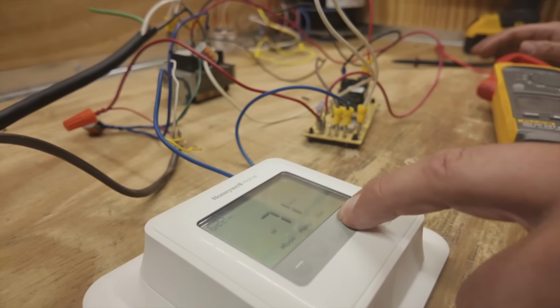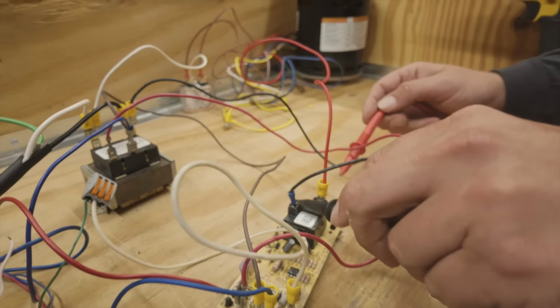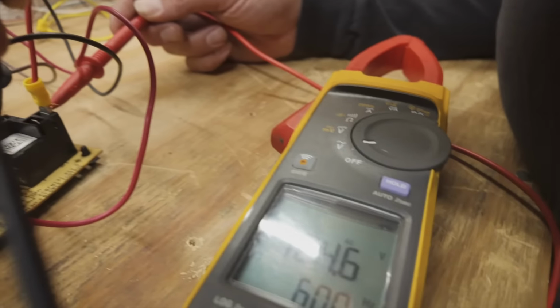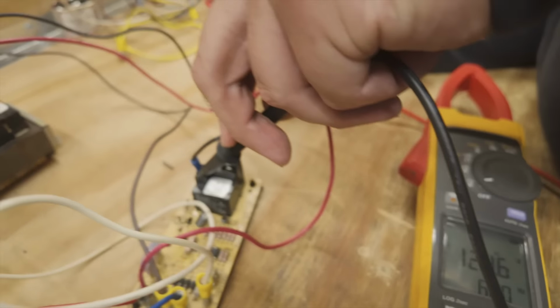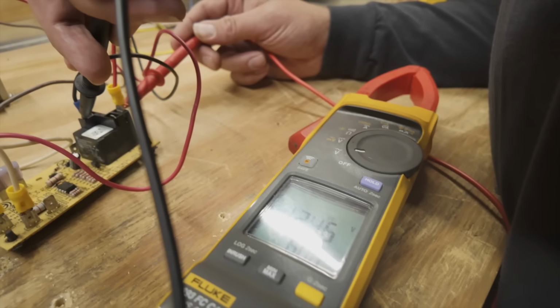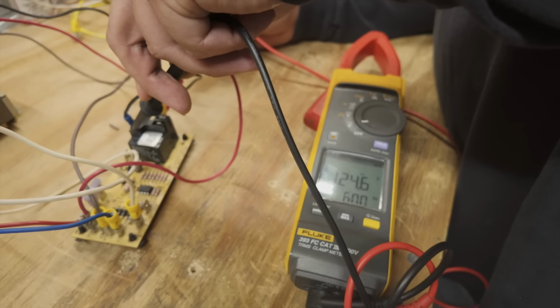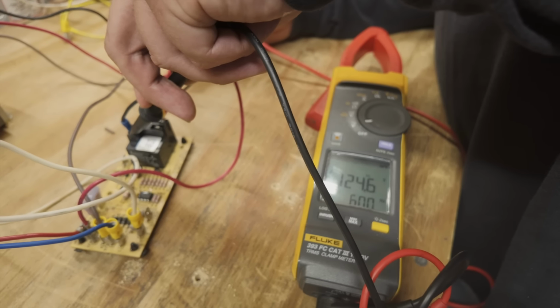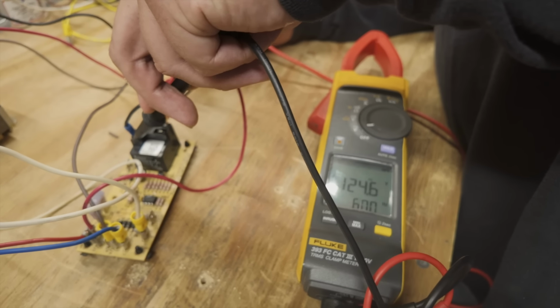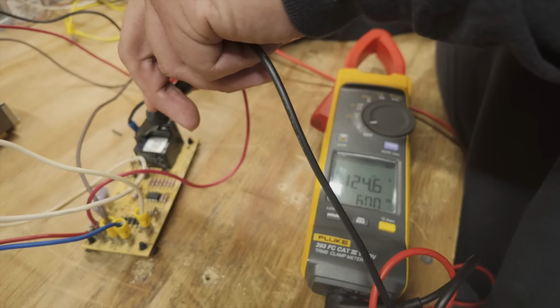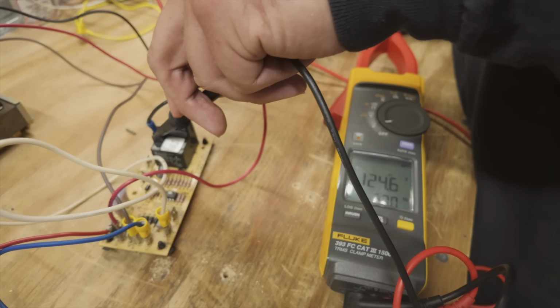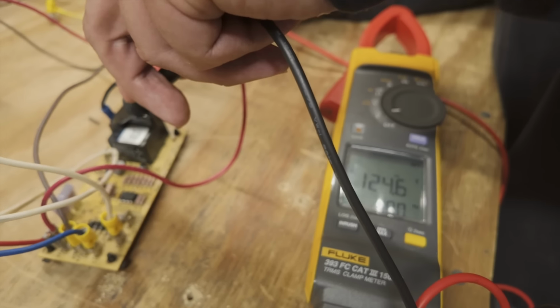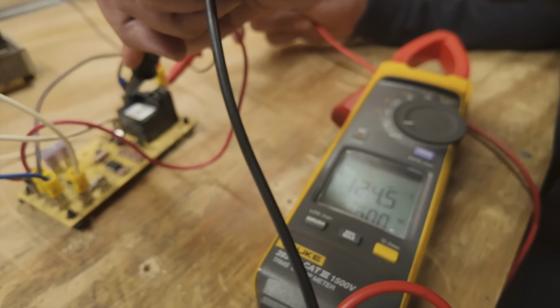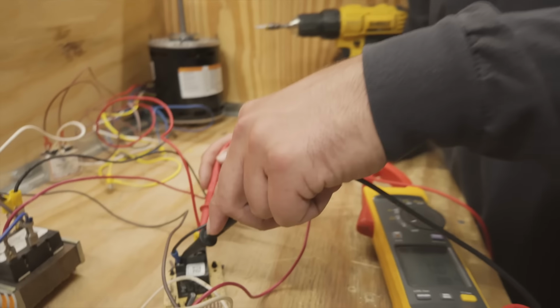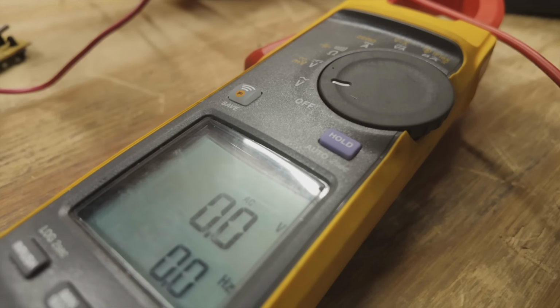Let's give it a call. And let's turn our meter to volts and check here to here. What do we got? 124. We just gave it a call, just clicked. Now the relay is going to close. We're waiting. You can do it. Got a little bit of a delay. Here we go. We got voltage, so we know it's not closed. We'll read voltage until it closes. We'll read 0 whenever it closes. Motor's on. The relay has closed. And look, 0 volts.